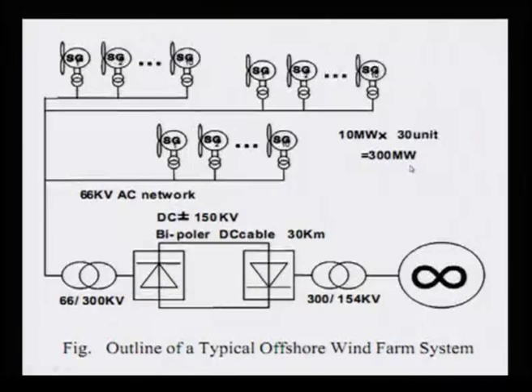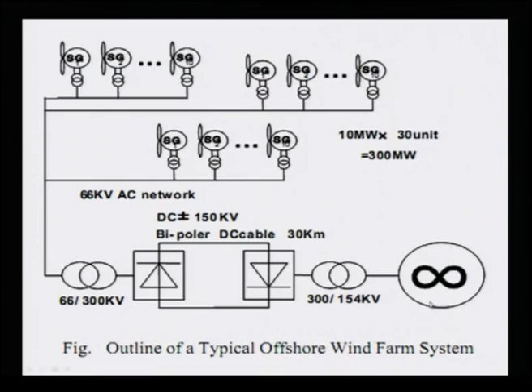If the fault occurs on the AC side here, there is a possibility of commutation failure, but with the help of this, it is not going to affect the other link. Without it, there would no doubt be commutation failure, but with it the voltage recovers because reactive power injection is maintained, and the system can be stabilized much faster. The constant AC voltage control makes the inverter produce reactive power to sustain the AC voltage on the inverter side, and the AC voltage can be kept higher than 0.9 per unit, which prevents the commutation failure of HVDC link 2.